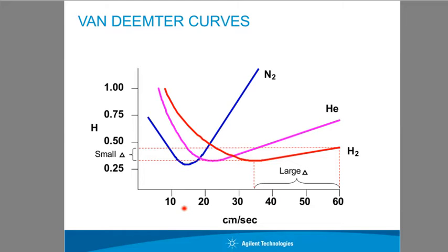So your analysis time may increase, not always, depending on what your analysis is, by going to nitrogen, because to get the most efficiency from the carrier gas, you're at a much, much slower velocity. And as you can see, the curve on either end is also a lot more abrupt. So the faster you go out, the less efficiency you lose essentially really, really quick.